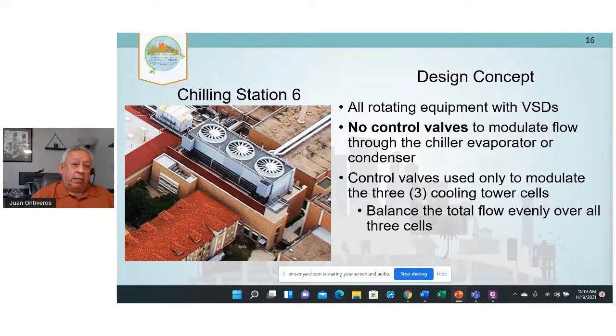Everything with VFDs. We would use no control valves to modulate flow through the chiller or the evaporator, because putting in a valve creates a flow restriction and you lose efficiency. We would only use control valves to modulate the flow across the 3 cooling towers, just to help us balance it. It was a very challenging plant to build, on a very constrained site. One of the challenges we had is that the tower really ended up being smaller than we wanted, and later on, I'll explain what problem that created.